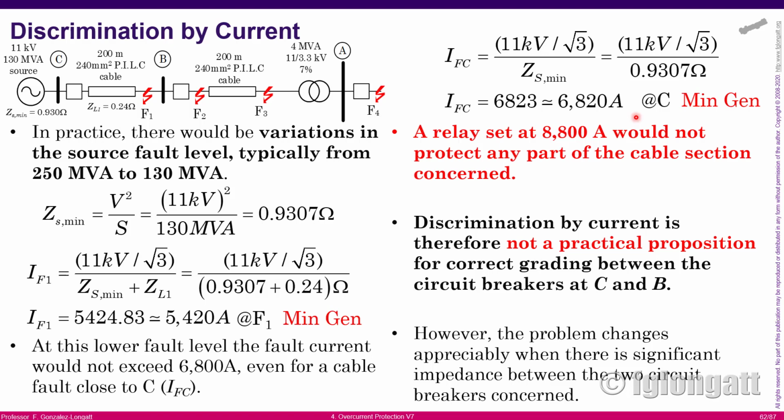Okay, again here there is a problem because there is no way to discriminate the current if we use the setting of 8.8 kiloamps.